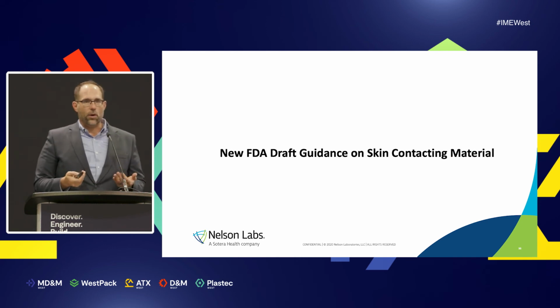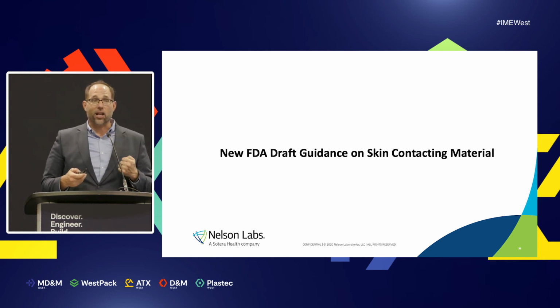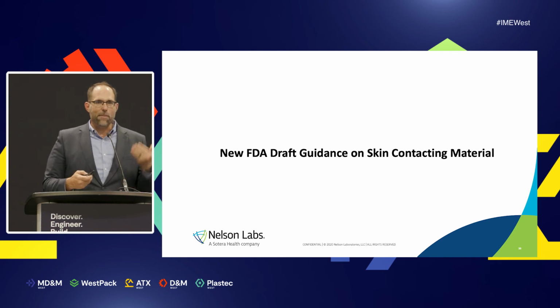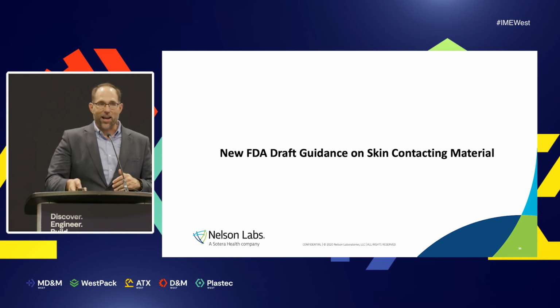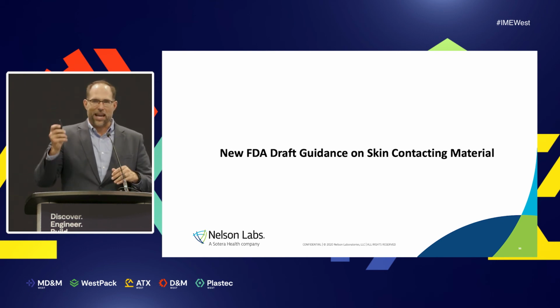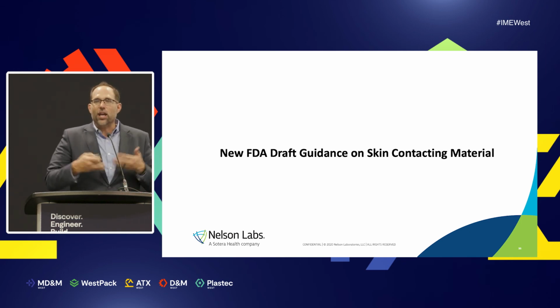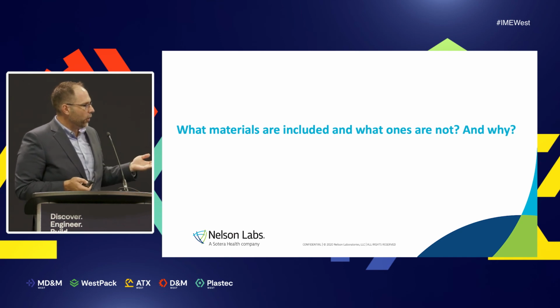Okay, so the last thing we're going to talk about today, and I've got 5 minutes to go through this, so I'm going to try to do it fast, is the new guidance document on skin contacting material. I love this guidance document. It makes me see that the FDA is thinking about a risk-based approach, right? Because they're saying, if your device contacts the skin, don't test it every single time. Look at the risk and look at the materials and justify if it needs to be tested. So, what materials are included in these and what not?